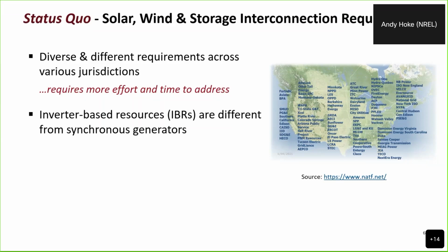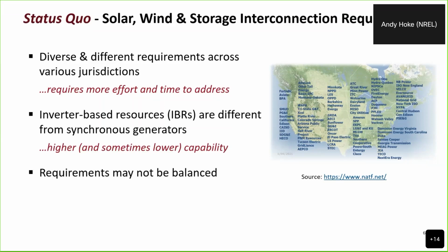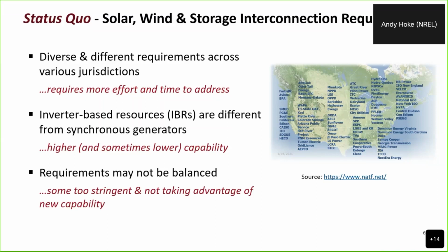And we're starting to realize that the grid is changing as we change from a grid that's typically based on synchronous generators to one that is more and more based upon inverter-based resources. And those resources have different capabilities. Sometimes they may have better capabilities. Sometimes their capabilities may have weaknesses relative to synchronous generators. And so we need to change the interconnection requirements to account for those different requirements. And of course, the requirements across different regions and across different technologies are not always balanced. And so IEEE 2800 tries to unify that across all the different transmission operators.